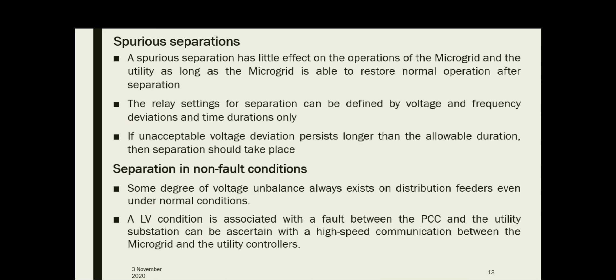The next scenario is separation in non-fault conditions. Low voltages may also occur under non-fault conditions; therefore, whether a low voltage condition is associated with a fault between the PCC and the utility substation may be difficult to ascertain without high-speed communication between the microgrid and utility controllers. Even without a fault, there is a possibility of low voltages, and we cannot differentiate whether it is due to a fault or not.